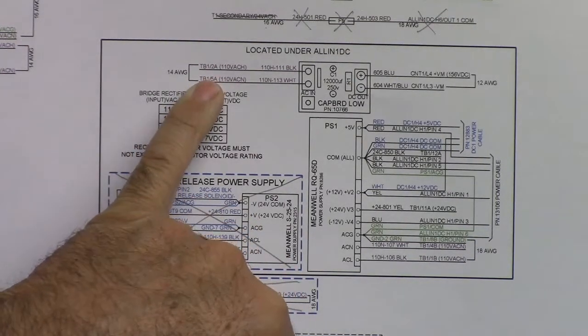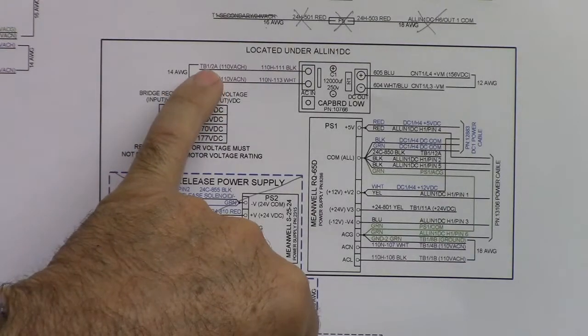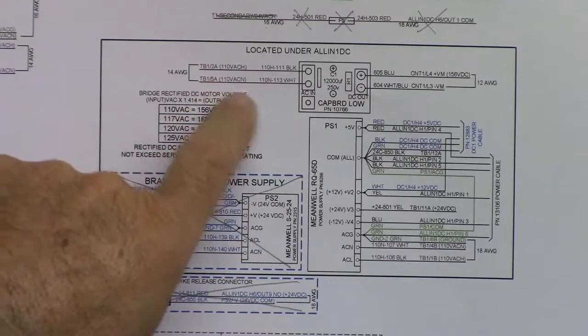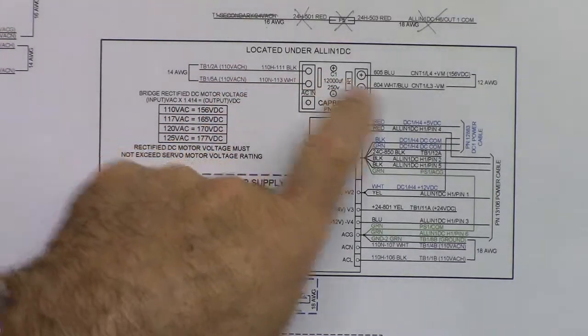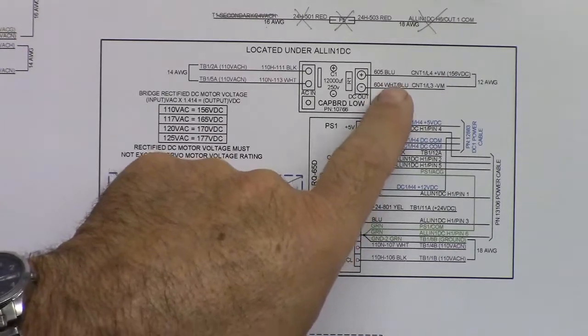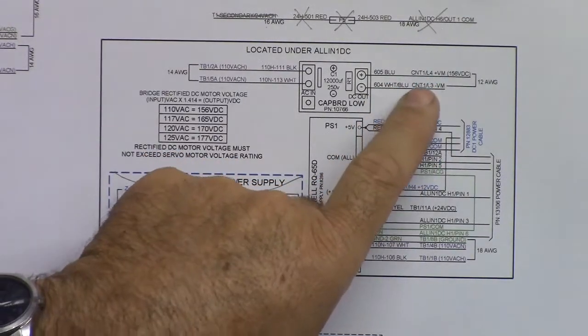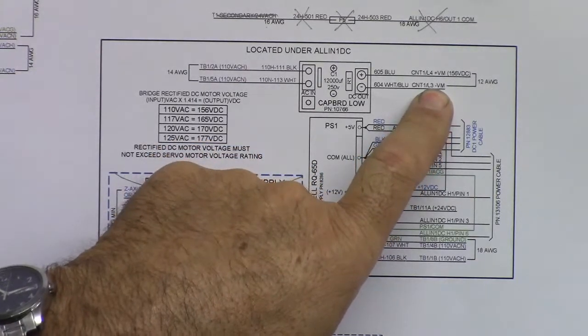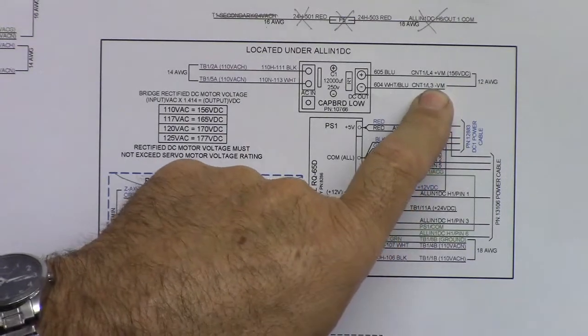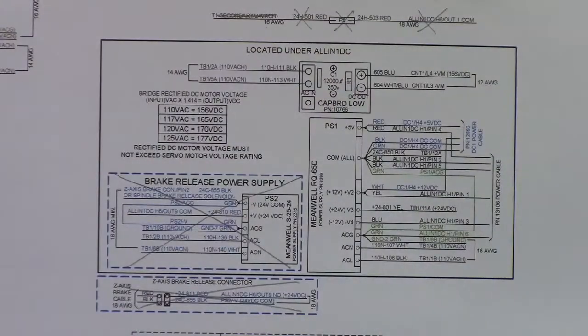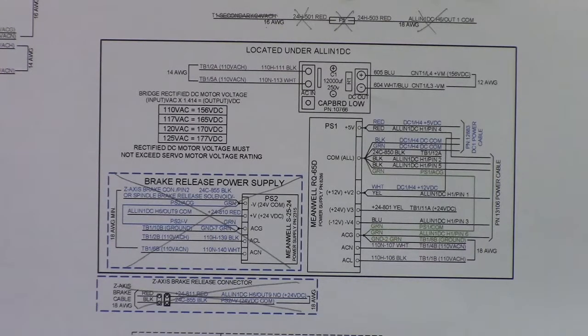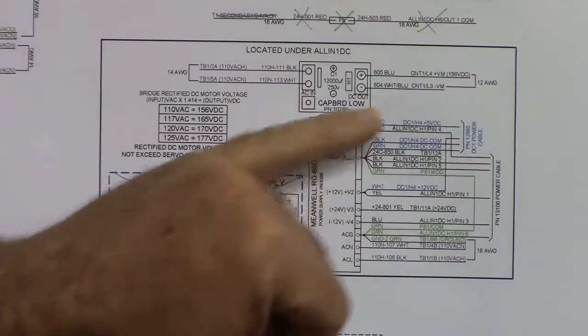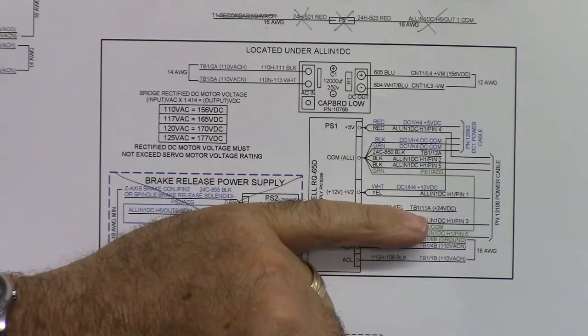On this side of the cap board, it says we're getting our power from TB12A, which is our AC positive, and then TB15A, that's the AC negative. It goes in, and on the outside, coming out of it is going to be our rectified DC, and it's going to CNT1L4 and CNT1L3. That's the CNT1 E-stop contactor we talked about previously, and then out of that contactor, it goes over to the all-in-one DC negative VM and positive VM input. That's the DC voltage for the servo motors.